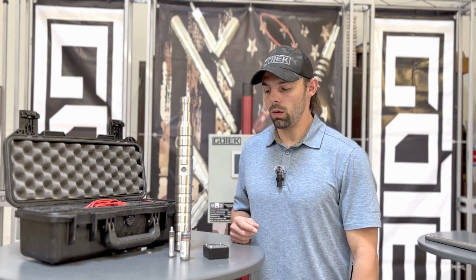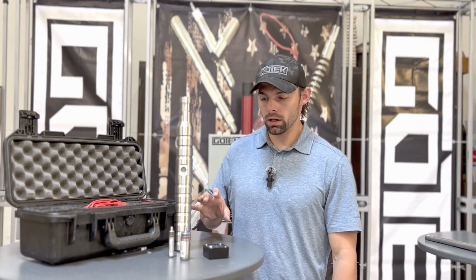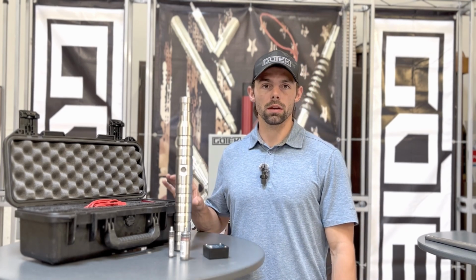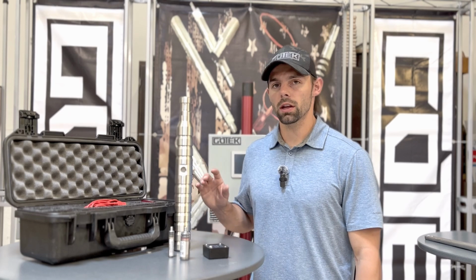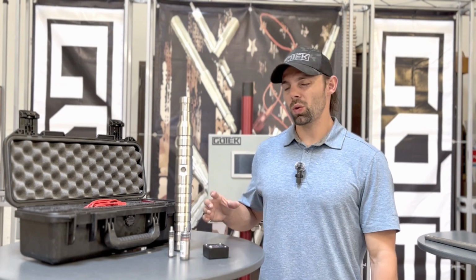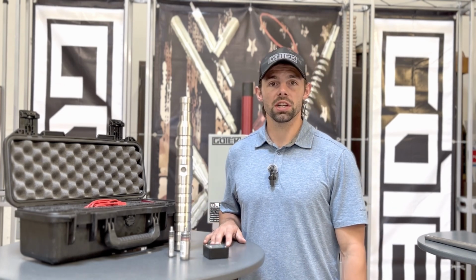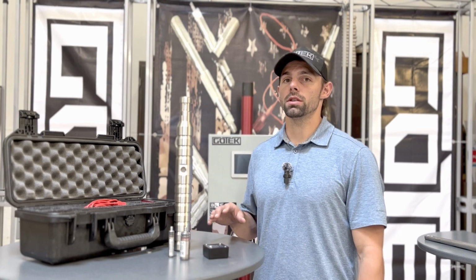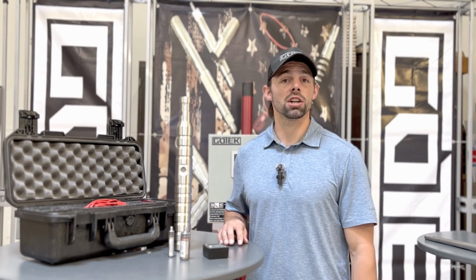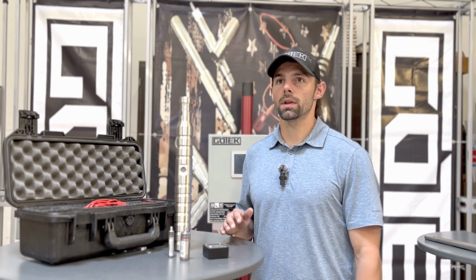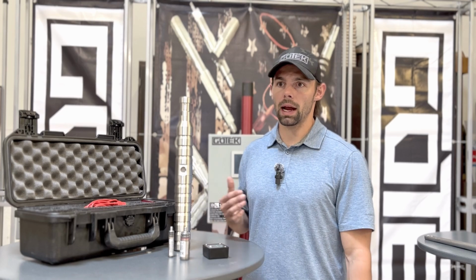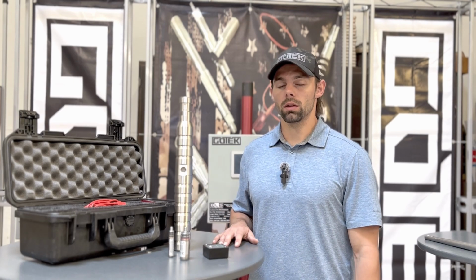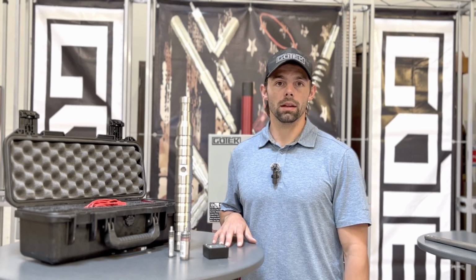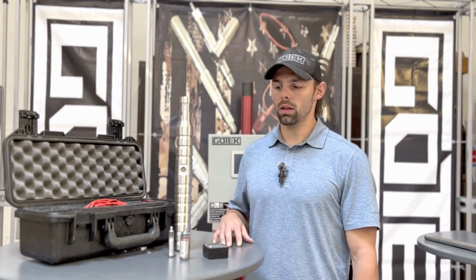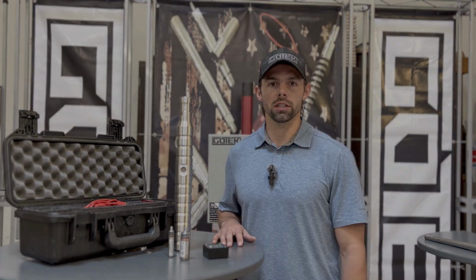One other thing to note is when the battery starts to die on the instrumented plunger as it's running, the board will not receive adequate voltage, and this can cause the unit to write what we'd call junk data. So if you get it back and your data looks really dirty, bad, or off scale, that's likely the cause.